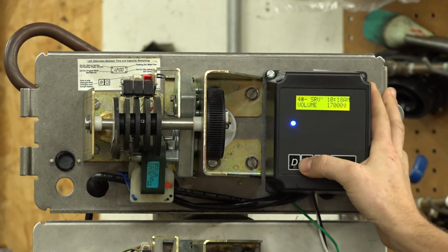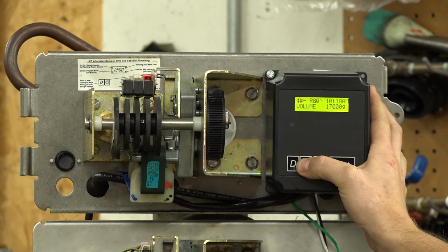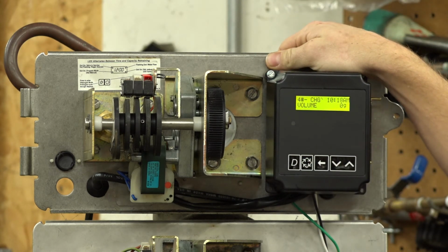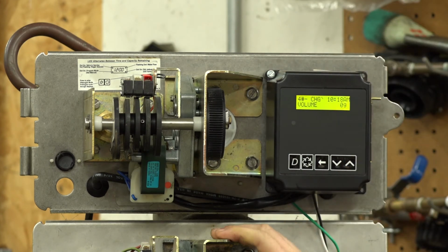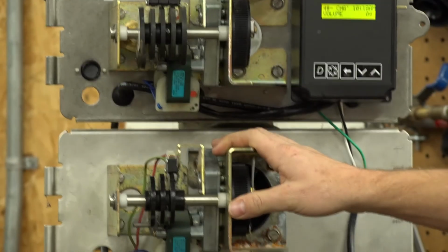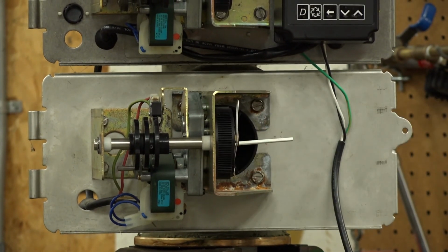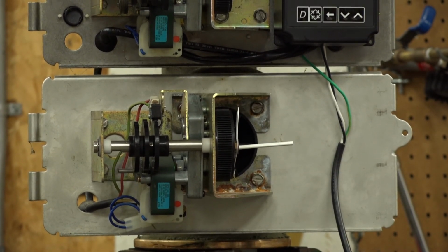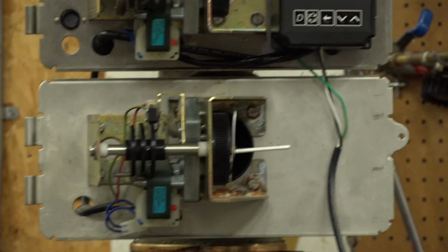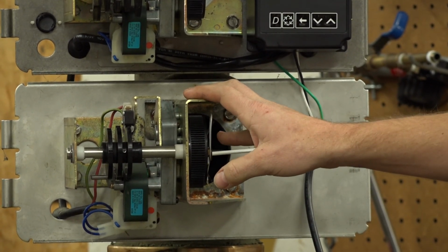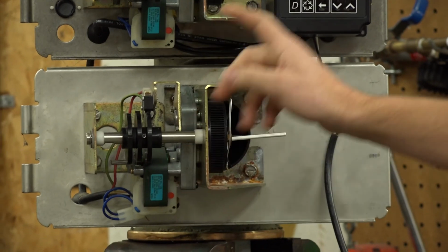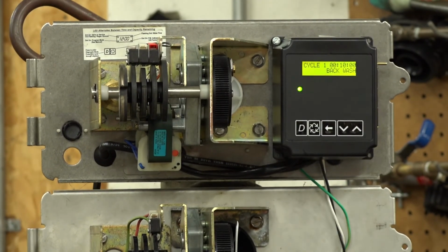So for example, we're going to press and hold the regeneration button. By pressing and holding it, we're going to start the motor. First thing to shift is always going to be your lower piston. On a twin, before the piston that's regenerating moves, the opposite unit is going to move out. It's going to come online. Then this one will move. So the first one shifted all the way in. Once it was in, the micro switch sent a signal to start the top drive motor.